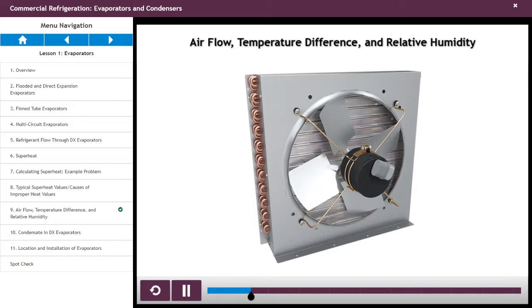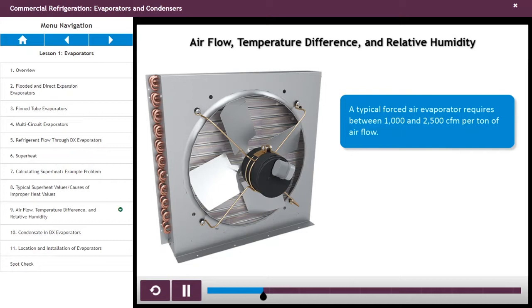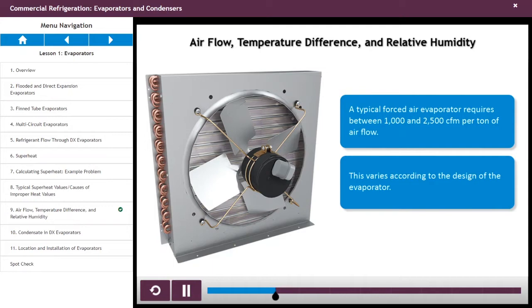A typical forced air evaporator requires between 1,000 and 2,500 CFM per ton of air flow, although it varies according to the design of the evaporator.